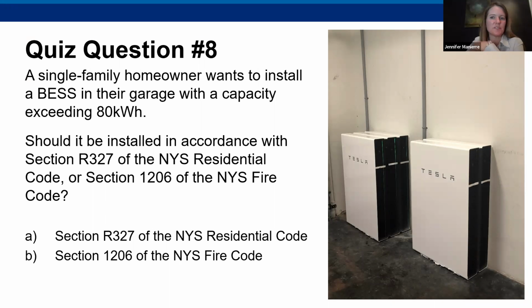All right, quiz question number 8, and then we're on to the final slide. If a single family homeowner wants to install a battery energy storage system in their garage with a capacity exceeding 80 kilowatt hours, should it be installed in accordance with section R327 of the New York State Residential Code or section 1206 of the New York State Fire Code, which is applicable to those more commercial systems? B, so they're exceeding commercial 80 code. It's B, it's commercial code. That is right, because they're exceeding that 80 kilowatt hour threshold, so they have to meet the more stringent requirements that are outlined in the commercial one.